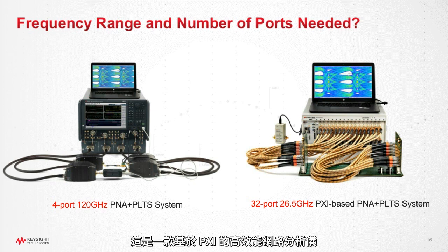This is a PXI-based performance network analyzer, and we use this industry standard chassis with plug-in modules, and each plug-in module that slides in vertically here is a 2-port vector network analyzer that can be scaled as your requirements are accelerated. So you can start this with just 4 ports and then expand it all the way up to 32.